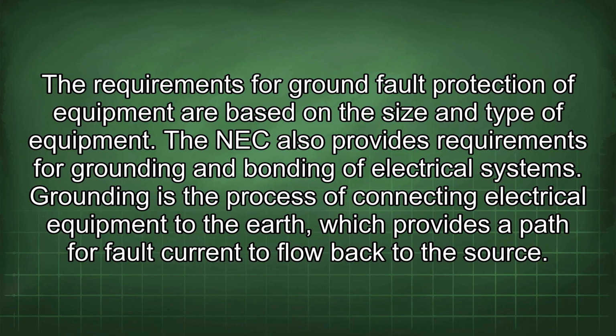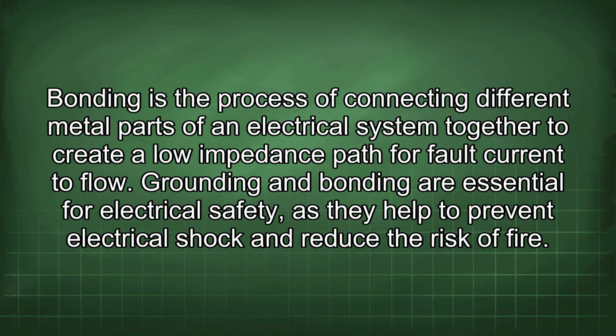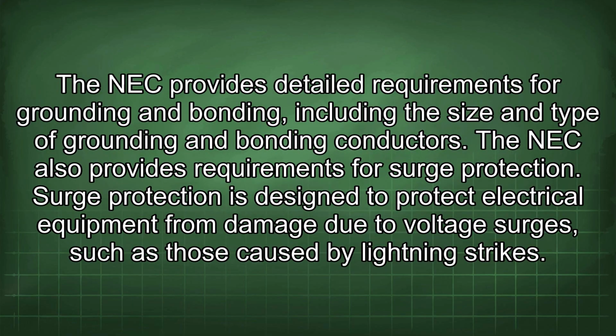The NEC also provides requirements for grounding and bonding of electrical systems. Grounding is the process of connecting electrical equipment to the earth, which provides a path for fault current to flow back to the source. Bonding is the process of connecting different metal parts of an electrical system together to create a low impedance path for fault current to flow. Grounding and bonding are essential for electrical safety, as they help to prevent electrical shock and reduce the risk of fire. The NEC provides detailed requirements for grounding and bonding, including the size and type of grounding and bonding conductors.